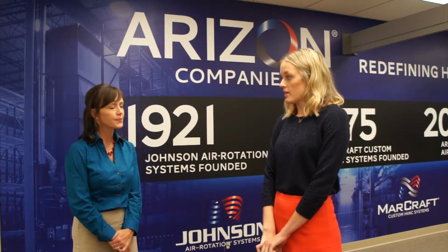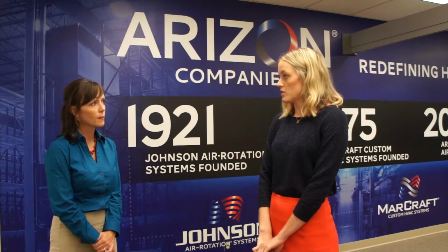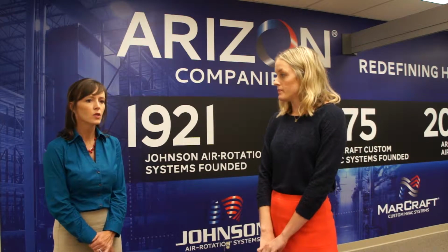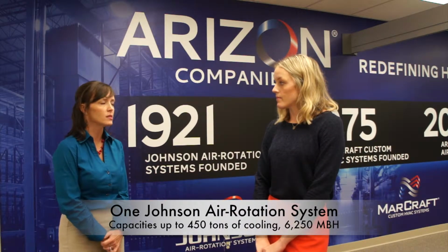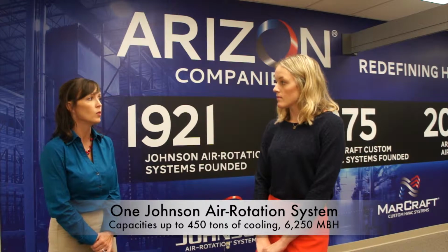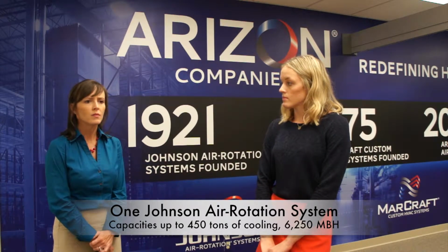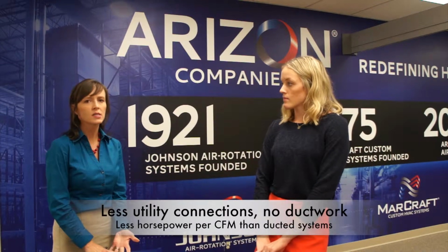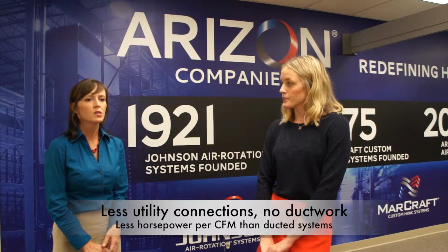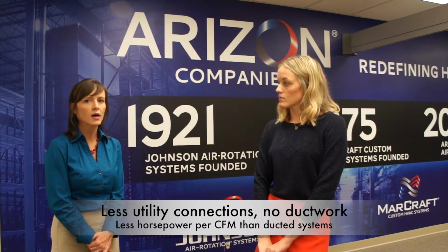And what are some of the benefits, would you say, for a Johnson air rotation unit? Well, normally for Johnson air rotation, as opposed to a traditional system like a rooftop unit, say you have a 100,000 square foot facility. If the locations are good, then we can generally get away with using one unit as opposed to a traditional rooftop system which might use 4 or 8 or even more rooftop units depending upon the temperature. Also, with less units, there's less roof penetrations, less utility connections, less gas connections, so the installation is easy and it's usually low cost.